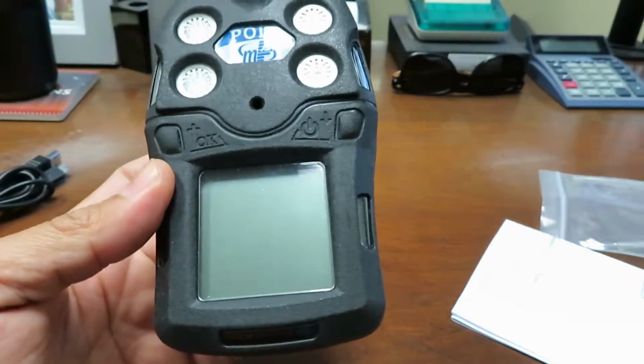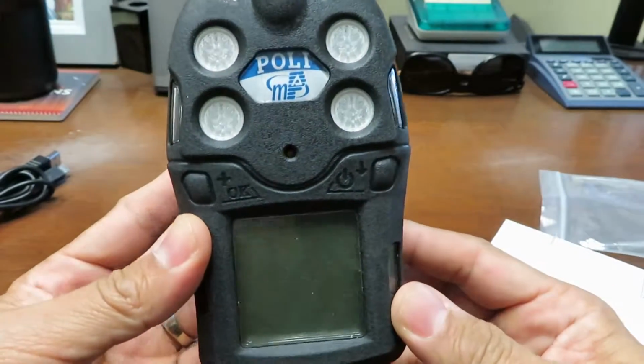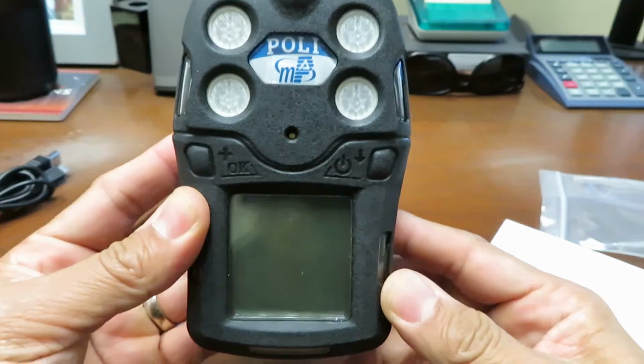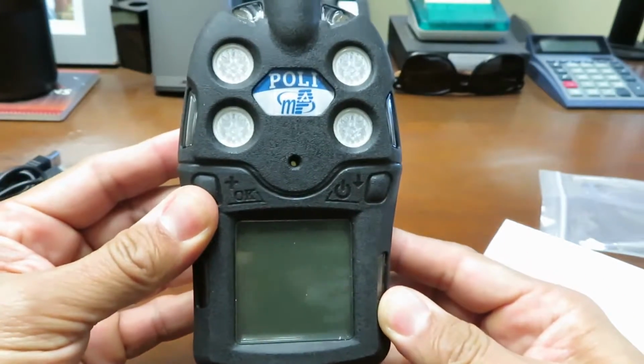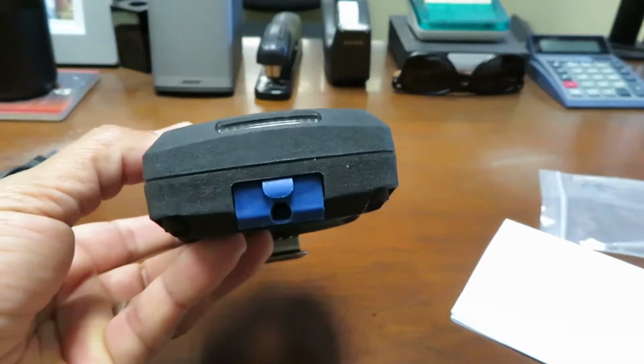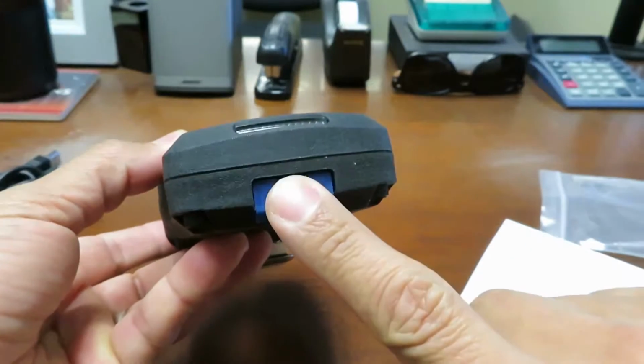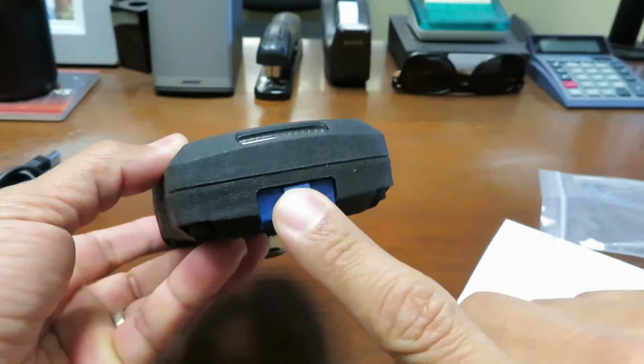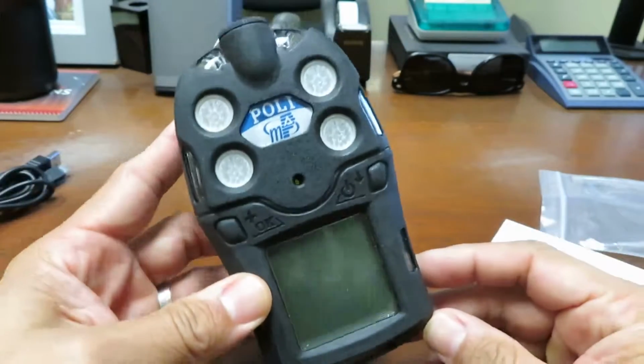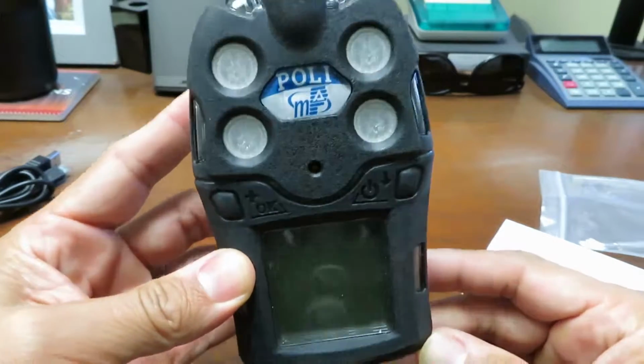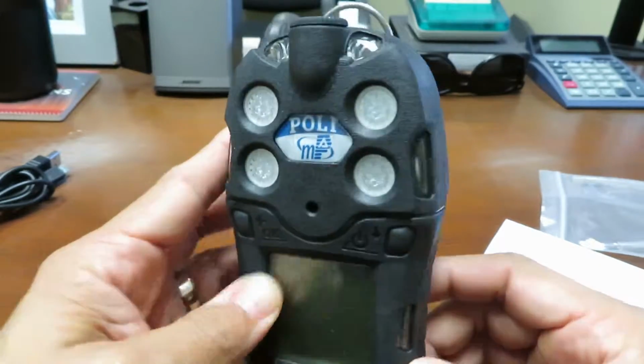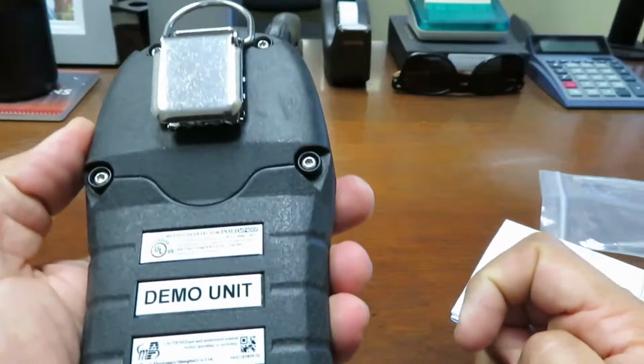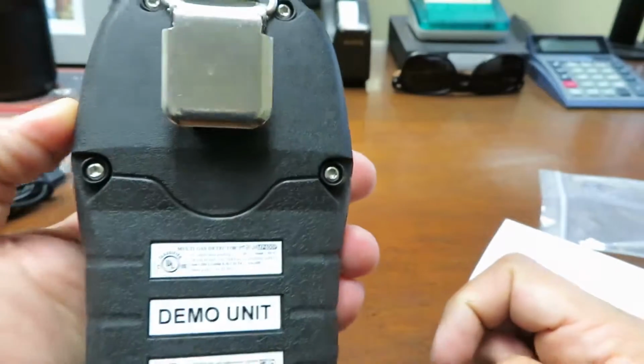It has continuous data logging for 6 months for 4 sensors at 1-minute intervals, 24 hours a day, 7 days a week. The charging and communication port handles charging, data download, instrument setup, and firmware upgrades from a PC or laptop via PC COM, a cradle, or the travel charger.